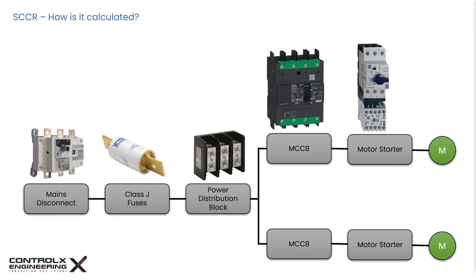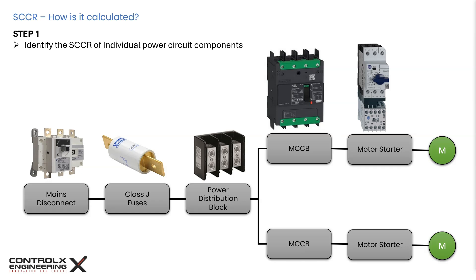Consider this simple circuit diagram. Power enters the control cabinet through the mains disconnect, then overcurrent protection fuses and power distribution blocks distribute incoming power to two branch circuits. Each branch is protected by a breaker, and motor starters control the two load motors. For Step 1, power circuit components are generally required to have short circuit ratings published, with certain components like voltmeters, EMI filters, and power resistors exempt per paragraph SB 4.2.1. SCCR values can be obtained from manufacturer labels, data sheets, or the default values in table SB 4.1, which lists standard default SCCR ratings for components that are not tested or marked.